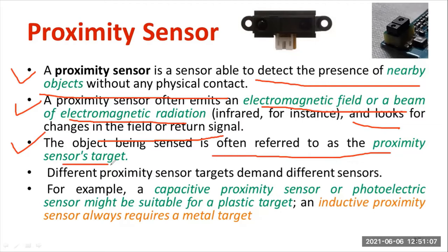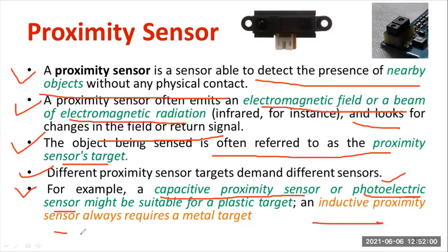Different proximity sensor targets demand different sensors; it varies depending on the requirement and what type of object you want to sense. It may be a metal object or a non-metal object. These sensors are most popularly used for sensing metal objects. Capacitive type proximity sensors are majorly used for identifying non-metal objects such as plastic, and photoelectric proximity sensors also detect non-metal objects. Inductive type proximity sensors are always used for identifying metal objects.